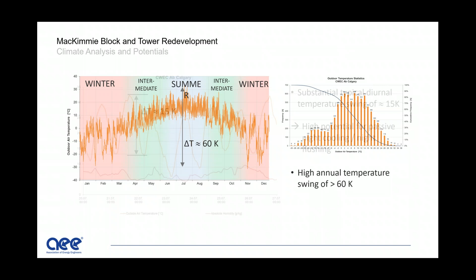The other thing we looked at was the diurnal temperature swing, the difference in temperature from daytime to nighttime. This chart shows outside air temperatures and absolute humidity through a representative period in summer, from July 20th through July 27th, a week of peak summer design conditions. You can see the delta T is about 15 degrees Kelvin or Celsius, from an overnight low below 15 degrees to a high during the day of over 30 degrees.